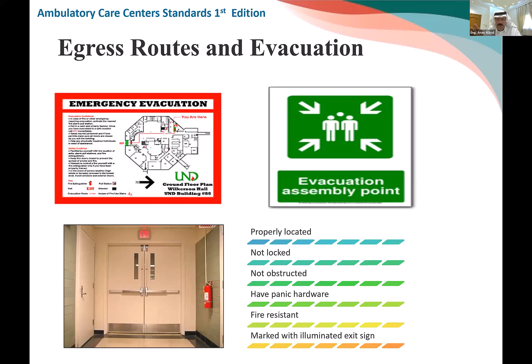Properly located, not locked. Now we need to differentiate between emergency doors and fire exits. Emergency doors could be fire rated or non-fire rated. Emergency exits are only for evacuating from the building. Fire rated steel doors are only used on the compartmentation walls. So not all emergency doors have to be fire doors. For fire doors, we also use them in electrical rooms and in staircases, to protect that space either from fire or to fire. So that's very important.